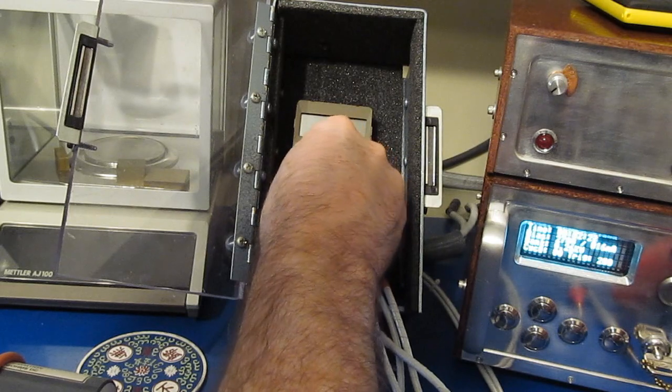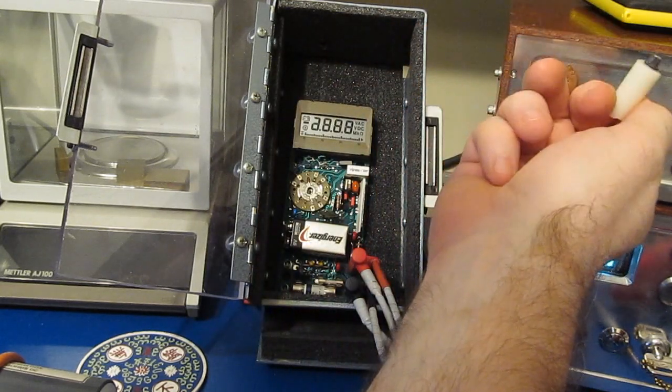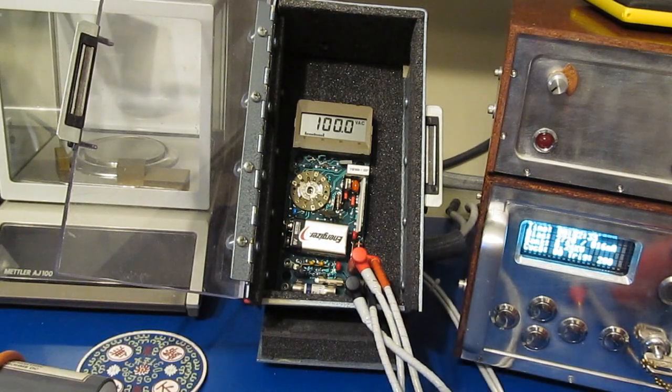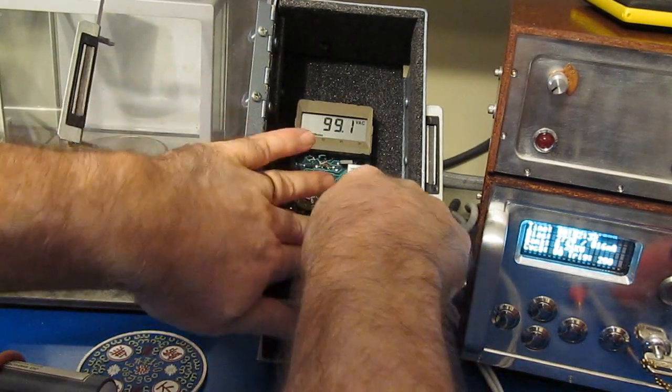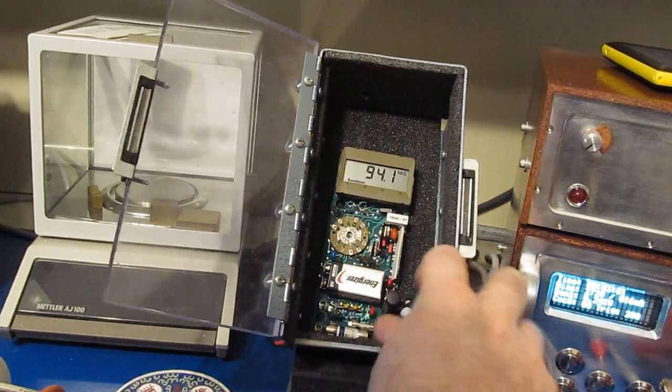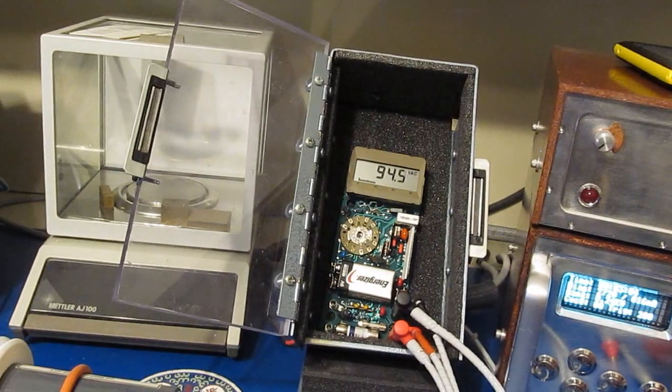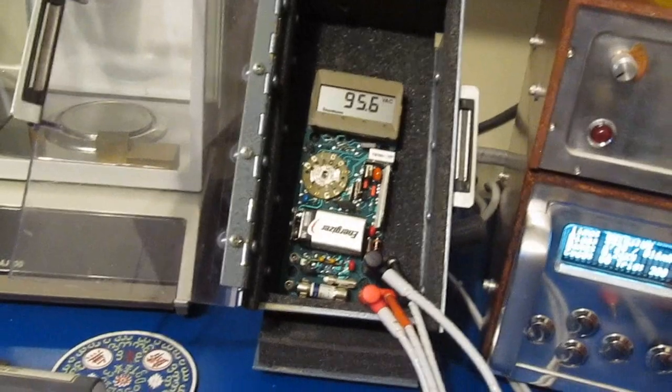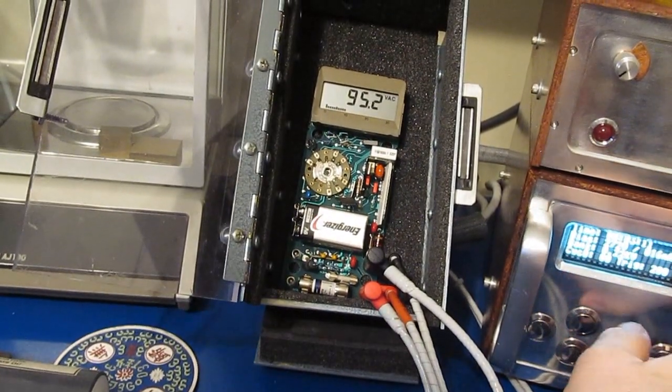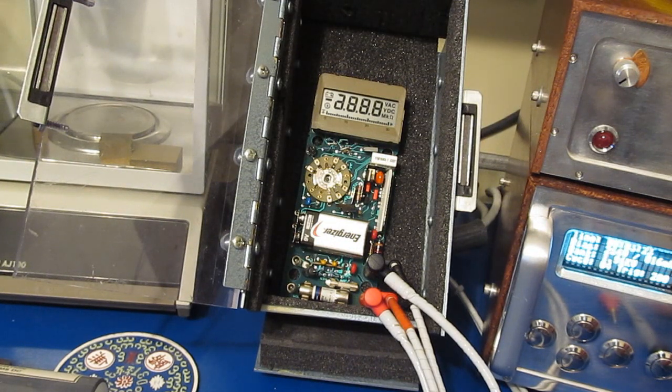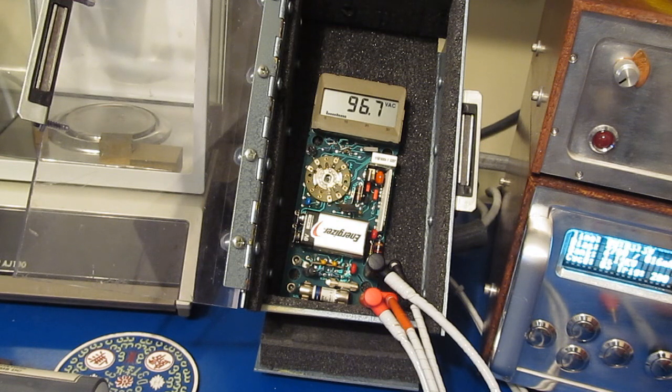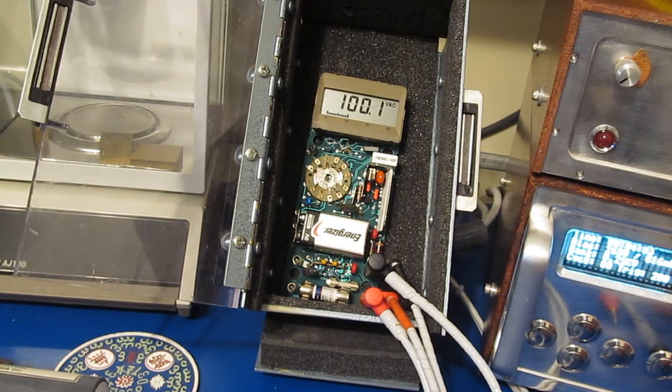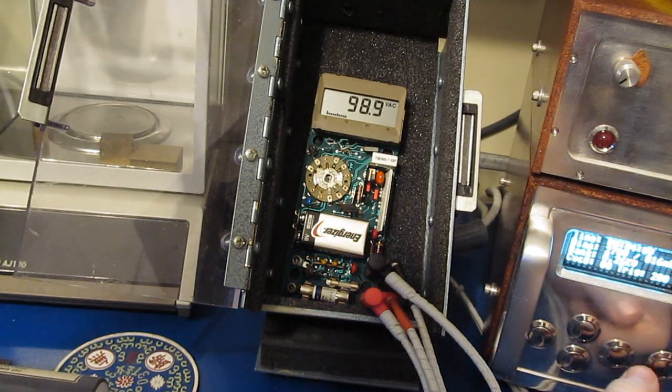And we'll turn it back on. Well it recovered. All right, let's try inverting it. Again, this will be four thousand volts peak, but this time a negative transient. Let's just bring the camera in a little closer and here we go. And we can see still reads the AC voltage just fine.